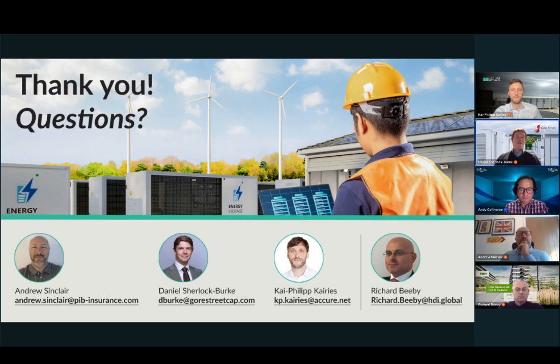I've seen a really great solution from one company where they have spark plugs going all the time. So as soon as you hit the lowest threshold for an explosion, it happens, instead of allowing a thermal runaway to continue and more explosive gas to fill up the container, giving you a larger bomb. So there's a lot of tech out there. It's not all going to lead to an insurance improvement, but it's stuff you should consider, because for the cost of it, generally, it's a pretty good benefit.